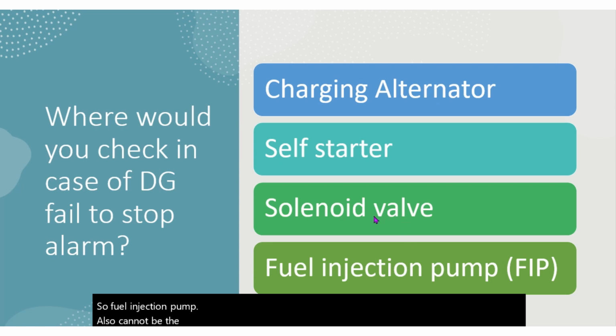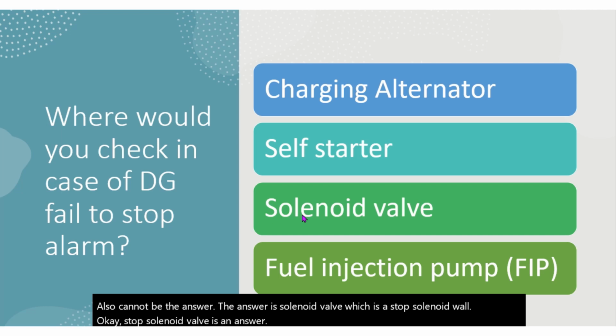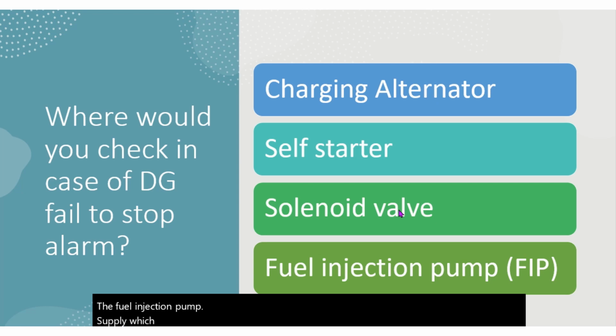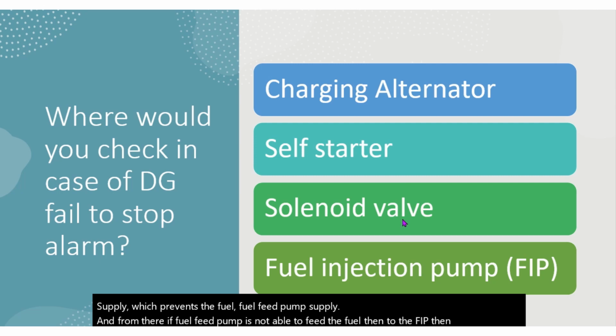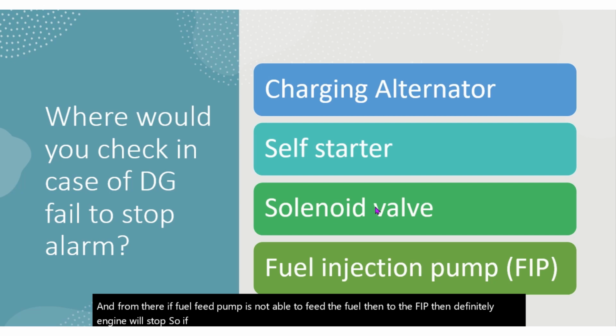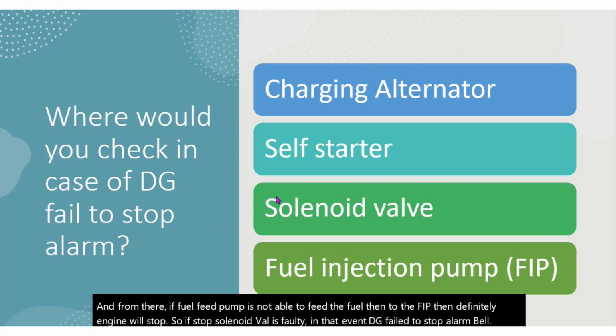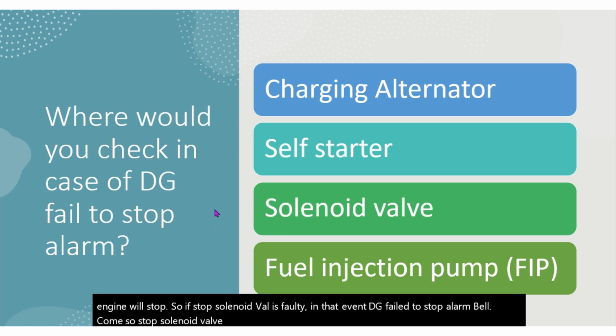The answer is the solenoid valve, which is the stop solenoid valve. The stop solenoid valve prevents the fuel supply to the fuel injection pump, which means the fuel feed pump supply is cut. If the fuel feed pump is not able to feed fuel to the FIP, then the engine will definitely stop. So if the stop solenoid valve is faulty, the DG fail to stop alarm will come. The stop solenoid valve is the answer to this question.